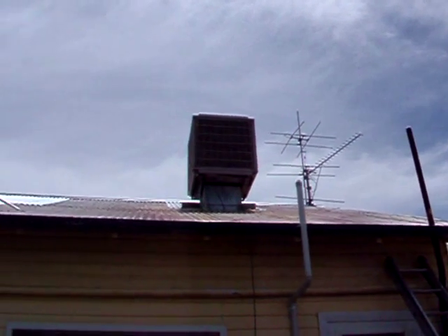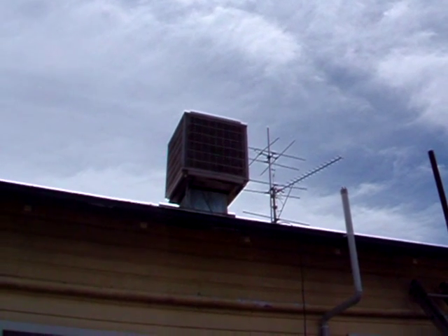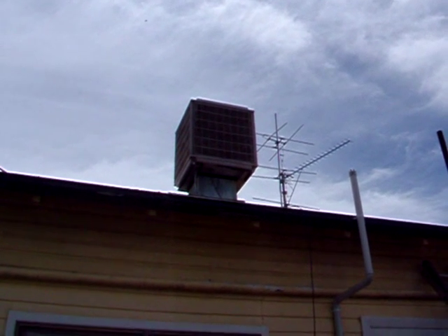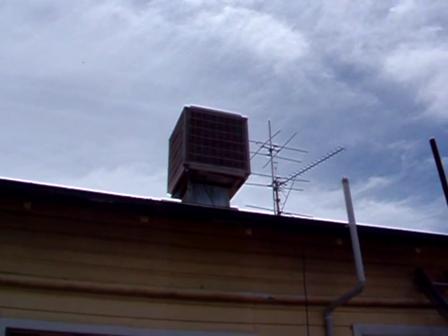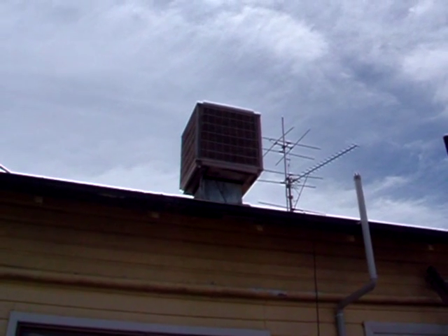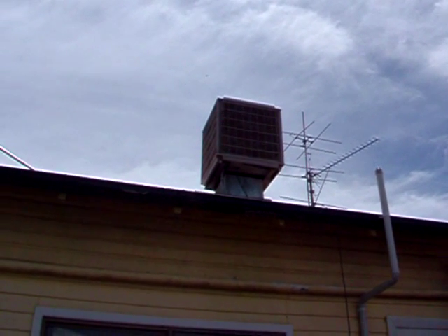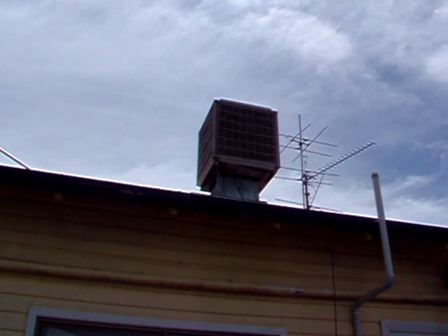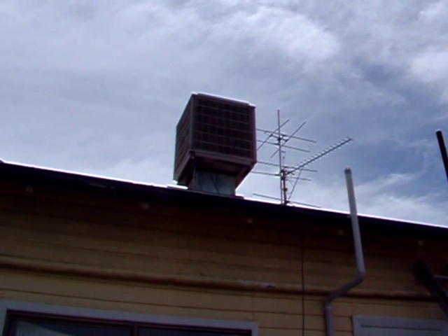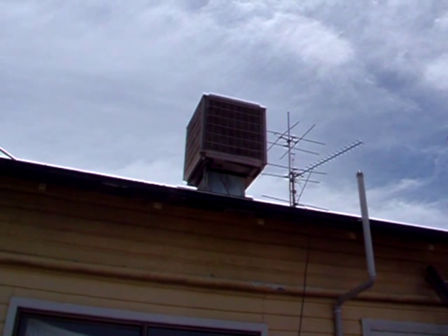So there's the unit on the roof with all the new pads installed. It's running at the moment - I don't know if you can hear it but it's reasonably quiet. I think I might need to replace the bearings in the fan at some stage. The kit is about $100 to replace the bearings, so that should last for probably 10 years. This one's probably been up there for that long and I'm sure it hasn't had anything done to it in that time. That will be the next project and I'll post an update to this video then.